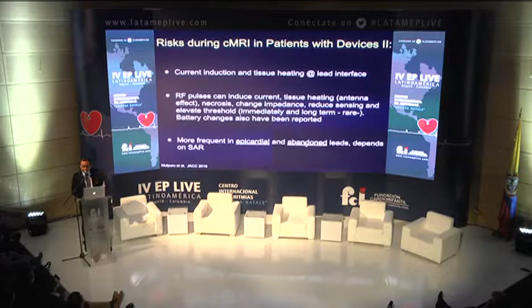The SAR is the specific absorption rate, and it is the radiofrequency power absorbed per unit of mass of tissue, watts per kilogram. This is a complex variable that depends on many things, and it is calculated by software from the average forward power passing into the RF coil and the body mass at the site where the radiofrequency is being transmitted.